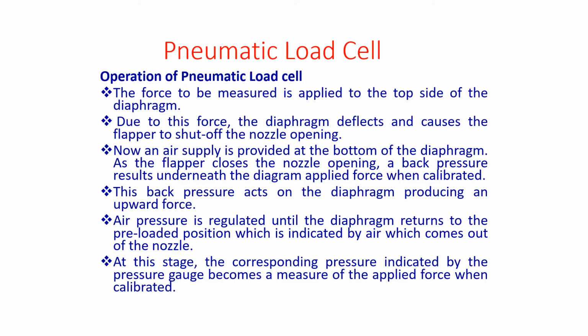Second one is the pneumatic load cell. This also works on the force balance principle. In the hydraulic load cell we used liquid, whereas in the pneumatic load cell we use air. As we have seen in the hydraulic one, here also the force to be measured is applied on the top side of the diaphragm. So the diaphragm deflects and causes the flapper to shut off the nozzle opening. Now an air supply is provided at the bottom of the diaphragm. As the flapper closes the nozzle opening, a back pressure results underneath the diaphragm when calibrated.